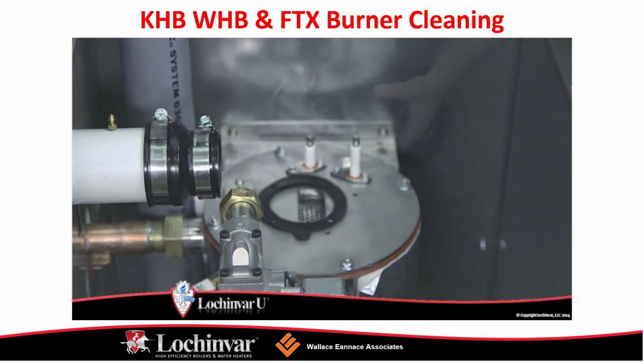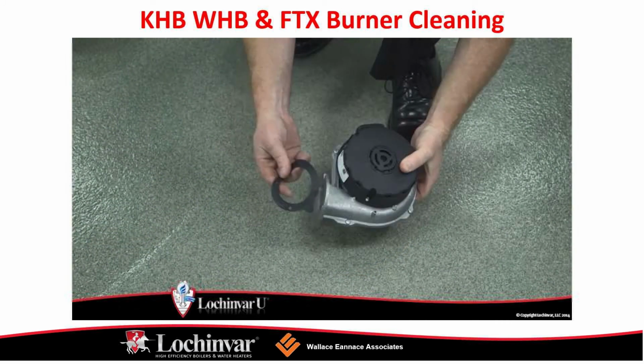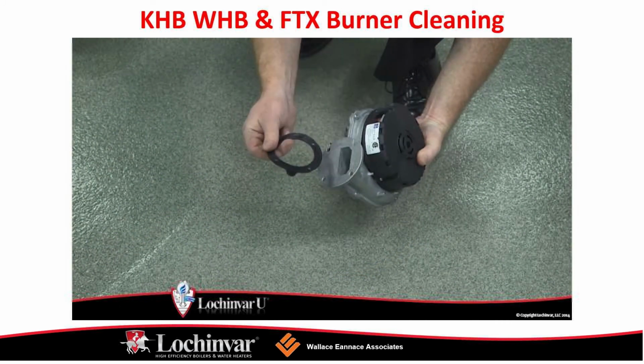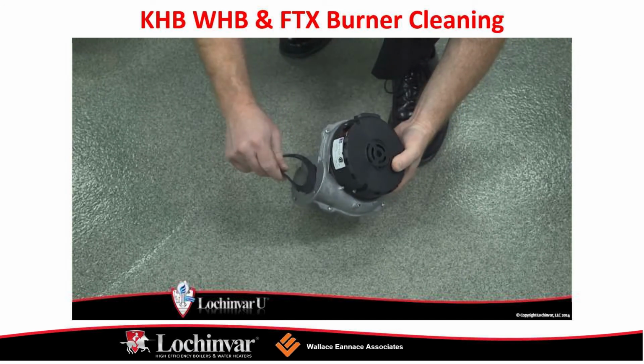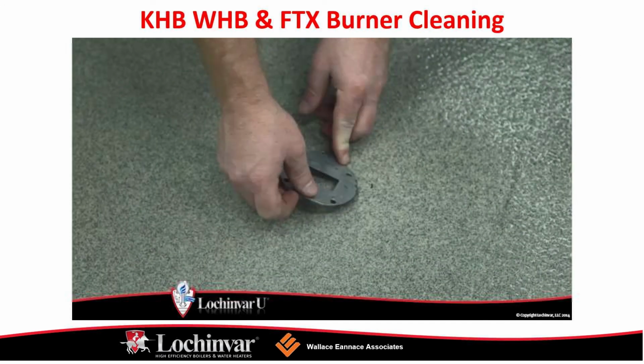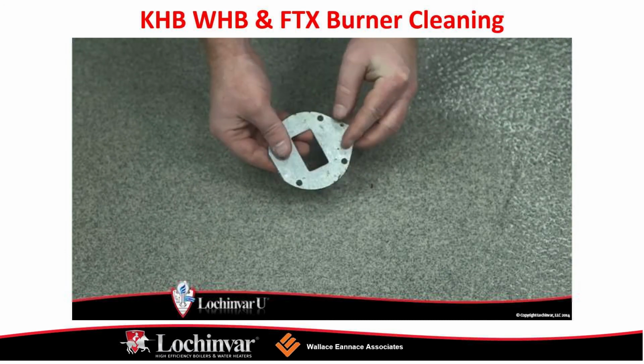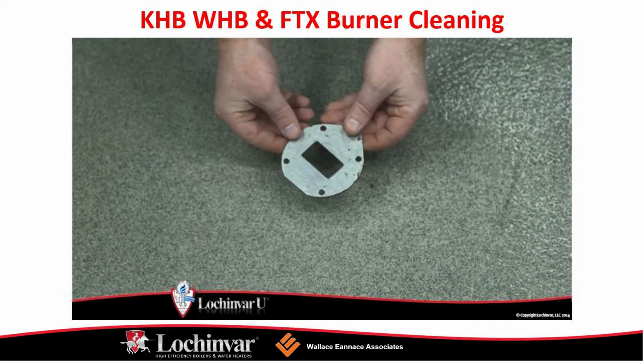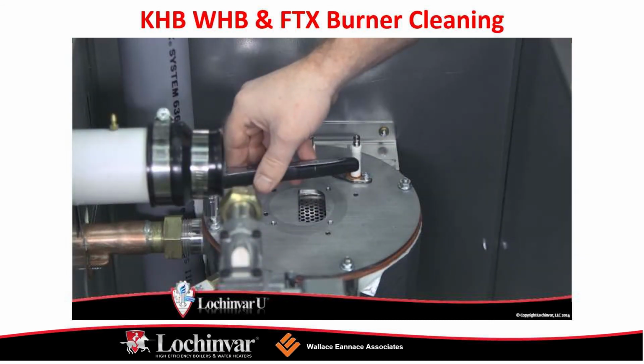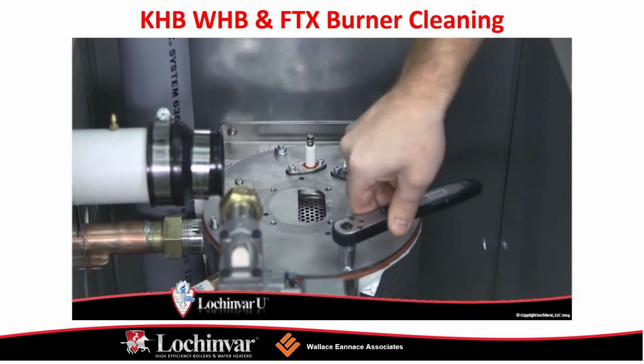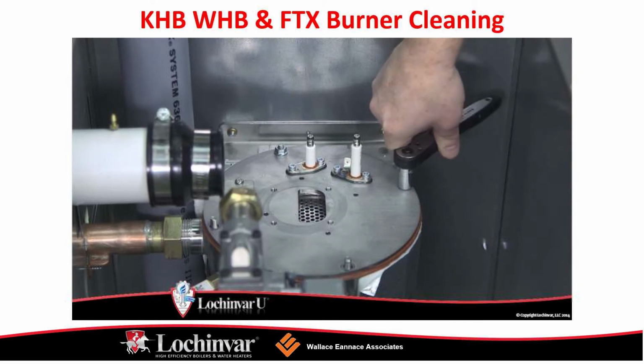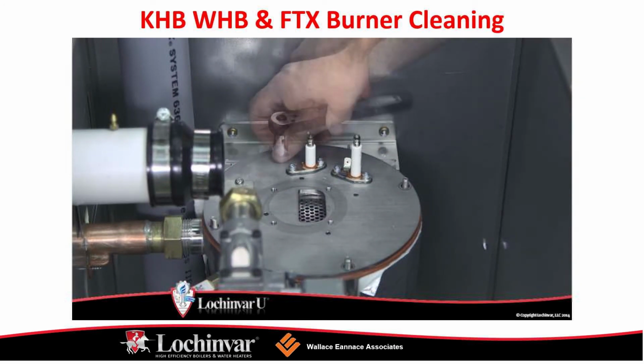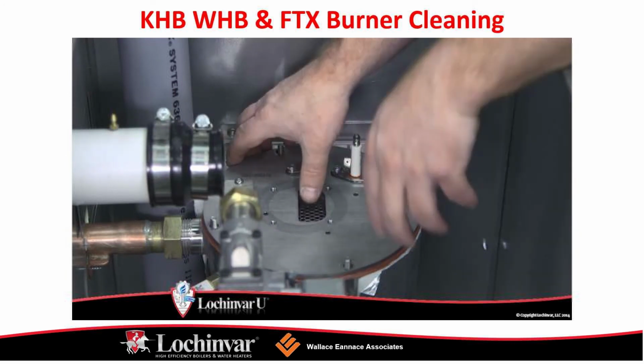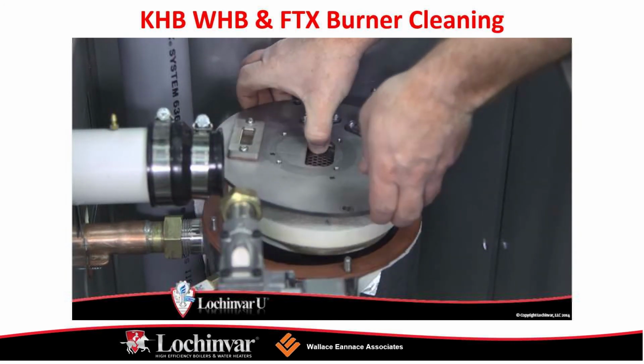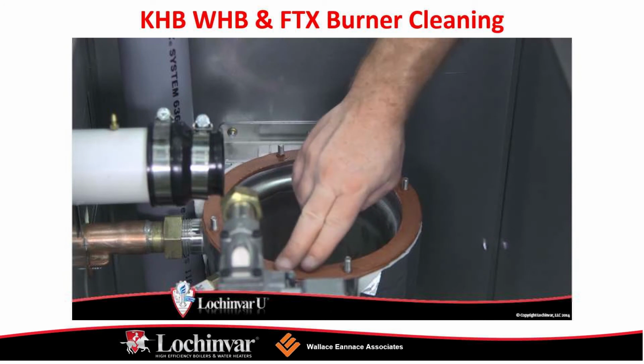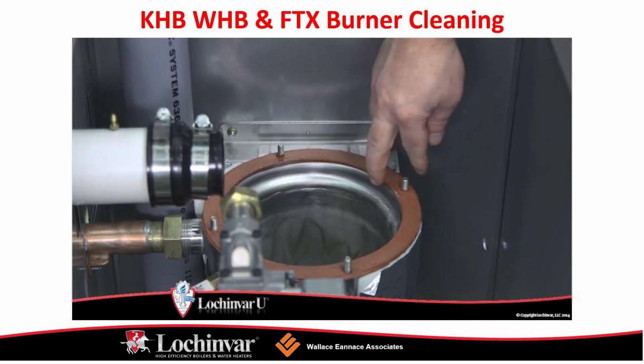Locate the ribbon cable from the display board to the main control board. Remove the cable from the control board. Using a Phillips head screwdriver, remove the 4 screws securing the bezel to the unit, and remove the bezel from the front of the unit. Then locate and disconnect the 2 wiring harness connections on the combustion blower. Now remove the wiring from the flame rod, spark igniter, and ground terminals from the heat exchanger door.